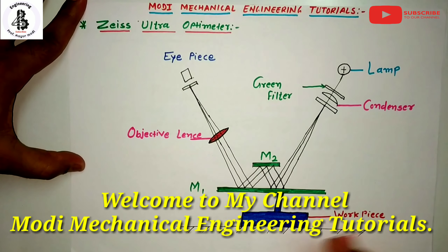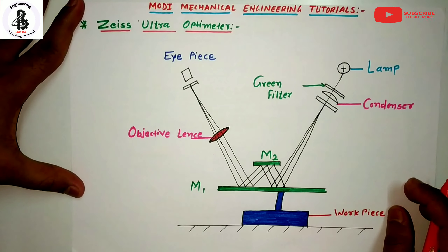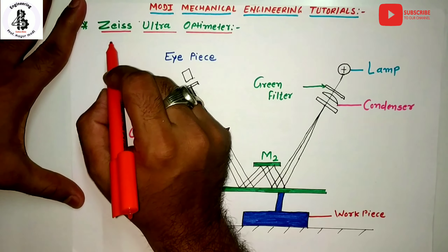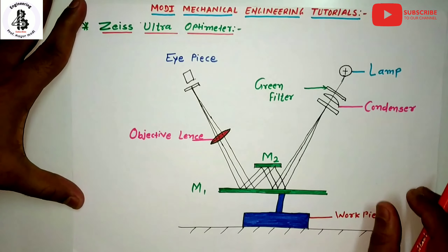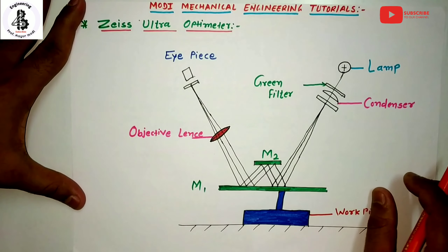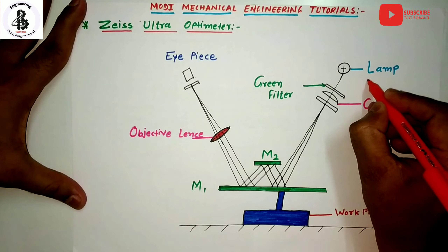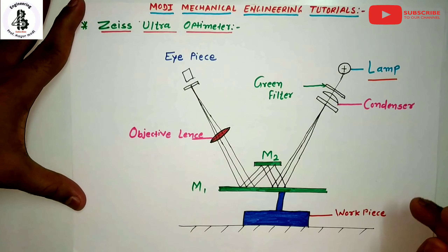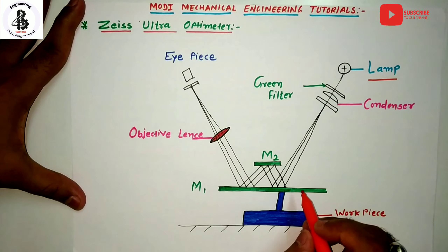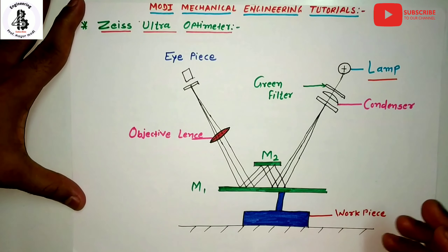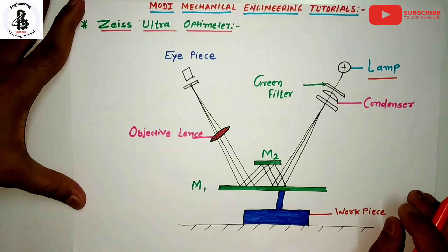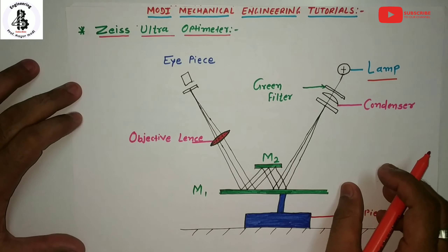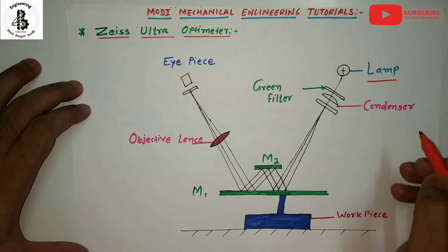Welcome to my YouTube channel Modi Mechanical Engineering Tutorials. Today I would like to explain about one of the comparators — the optical comparator — and its name is the Zeiss Ultra Optimeter. You can see the basic construction of the Zeiss Ultra Optimeter. The double reflection method or mechanism is adopted for measurements of workpiece materials, giving higher magnification compared to any other comparators.